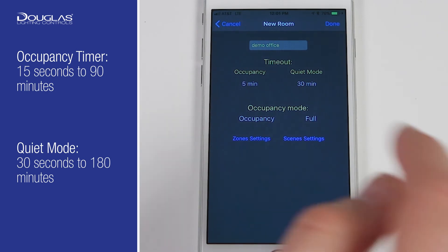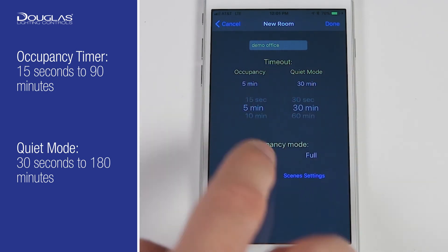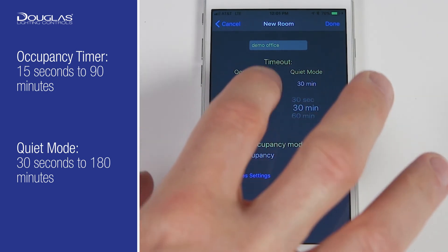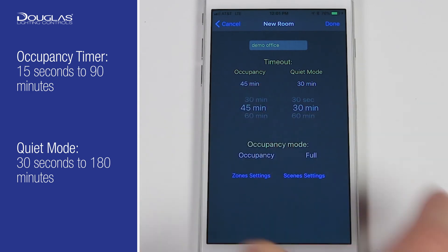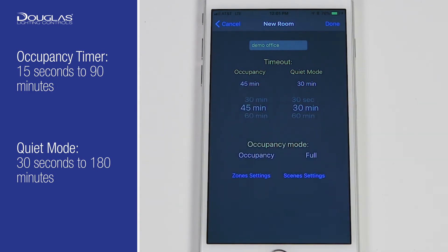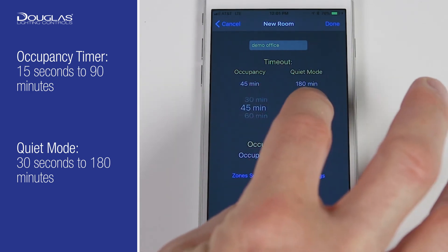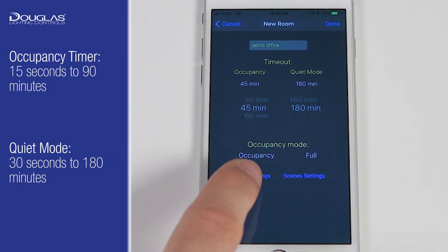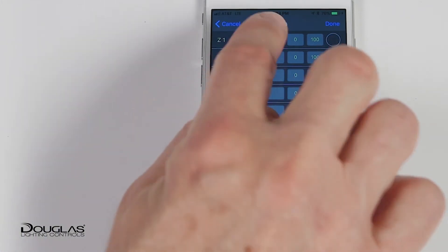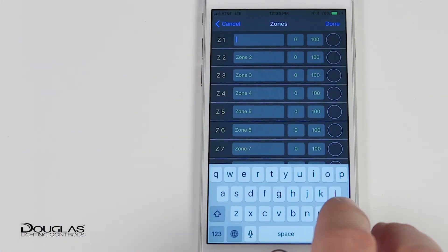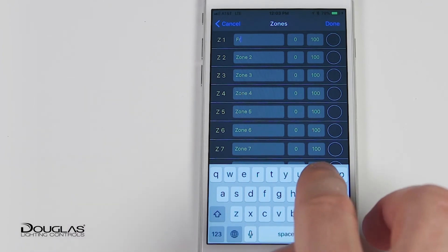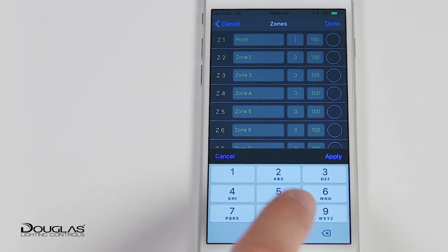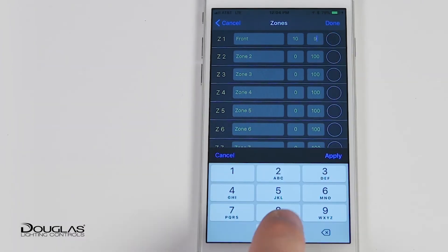Occupancy timer can be set from 15 seconds to 90 minutes. Quiet mode, which is used to override the occupancy sensor, can be set from 30 seconds to 180 minutes. This page is where the number of zones are identified and can be named. There is a maximum of eight zones in a room. Trim levels for the zones can also be set on this page.